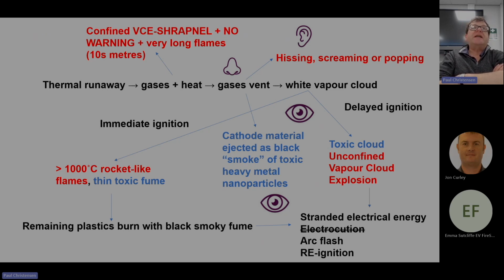If, however, the gases vent, the first thing you will hear is a loud popping noise, then typically a screaming or hissing noise. You'll see the black smoke come out first, which isn't smoke, it's the heavy metal nanoparticles or the contents of the cells. Then you'll see the white vapor cloud. If that ignites immediately, 1 to 2 meter long flames, 1000 to 1200 degrees centigrade.